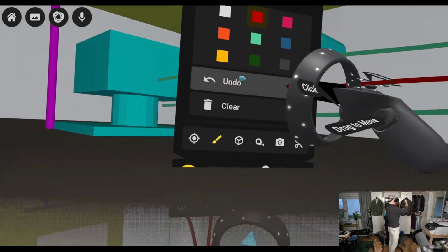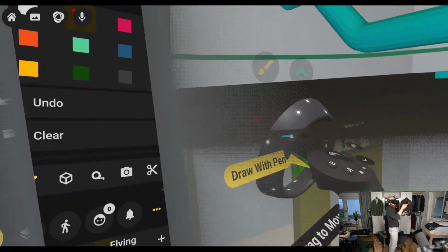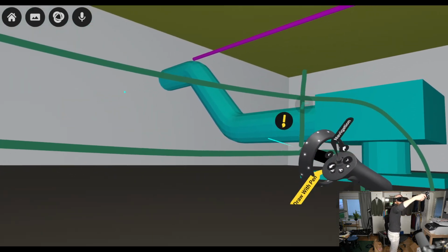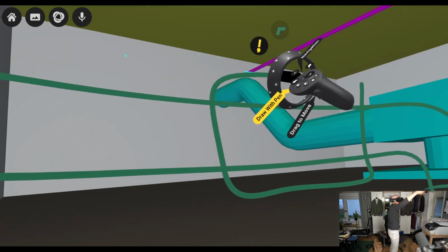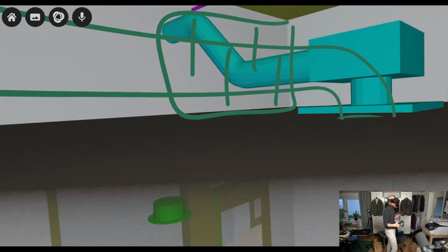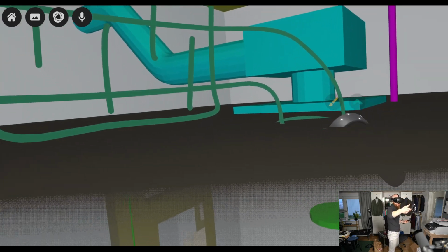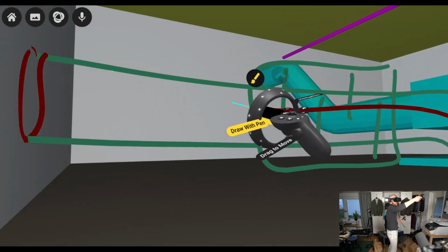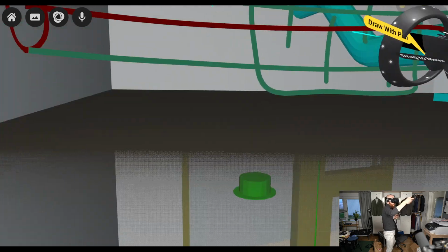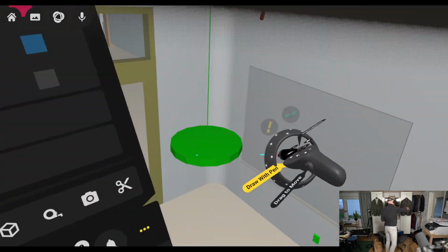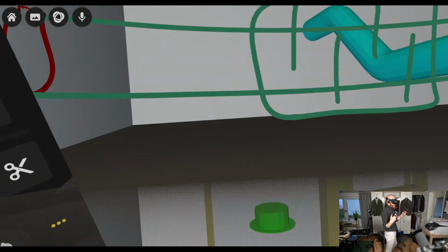So what do we do? Let's get rid of that one. What we can do there is to add a silencer. So let's say we put a silencer here on our channel. We draw it like this. Sound silencer. Great! Now we have perhaps eliminated this path, because now it has to pass through the silencer, and it will be attenuated here, hopefully enough so that there is not enough to cause a problem on the other side.